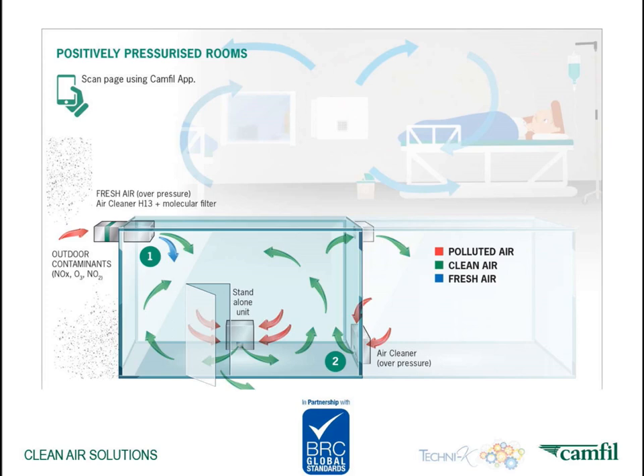In solution number one, as you can see in the upper left corner of the room, is the internal air cleaner configuration. So you have an air cleaner within the room. It's ducted to the other side of the room or to the outdoor air. And this actually creates the positive pressure, which you can see in the green arrows. In solution number two, as you can see in the right corner, here is the external air cleaner configuration. Then you can have an air cleaner on the other side of the wall of a room, make a hole, duct it, and supply the clean HEPA filtered air into the room. And now we are creating positive pressure. And you can see in the door opening, the green arrow of overpressure released through the door.